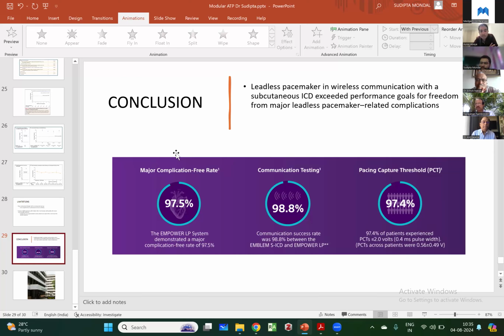One point I would like to emphasize to the audience is how this communication occurs. When they say wireless, it's not Bluetooth, it's unidirectional conductive communication. Impulses are sent from the shock coil, which is on the sternum, to the can, and they've repurposed a lead integrity kind of algorithm that they had. When the device detects an arrhythmia and wants ATP to be delivered, it sends these communication signals from the shocking coil to the can, and this is intercepted by the leadless pacemaker. Technically, the communication vector should be parallel to the leadless pacemaker placement. In practice, most of us put leadless pacemakers on the septum, so it comes right in the communication vector.